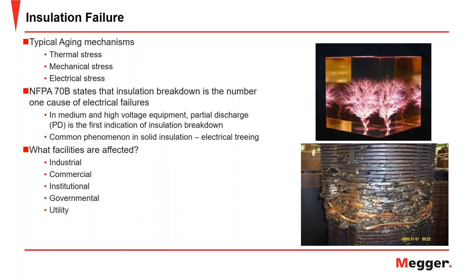This particularly means a lot in terms of partial discharge, because when it comes to medium and high voltage equipment, partial discharge or PD activity is one of the first indications of deteriorating insulation. This is commonly seen in solid insulation with the phenomenon of electrical treeing, which is a damaging process due to partial discharges that progresses through a stressed dielectric insulation. So for instance, here you can see where it would have started and stressed and treed through the solid dielectric or insulation. And if it were to go completely through, bridging both sides and causing ultimate failure, you could see a catastrophic event such as this blown out winding down here.